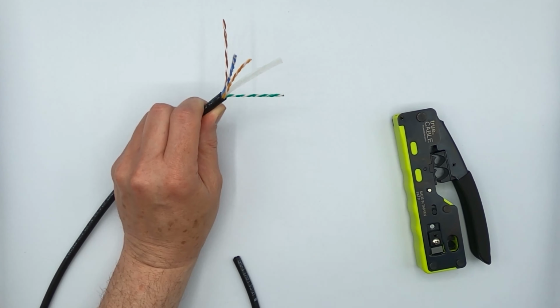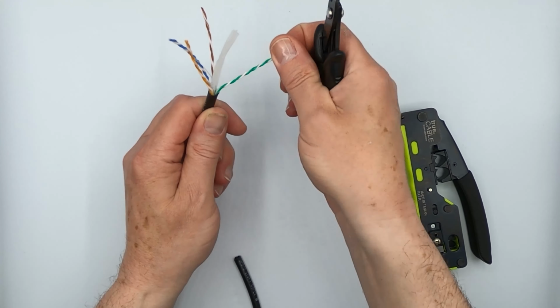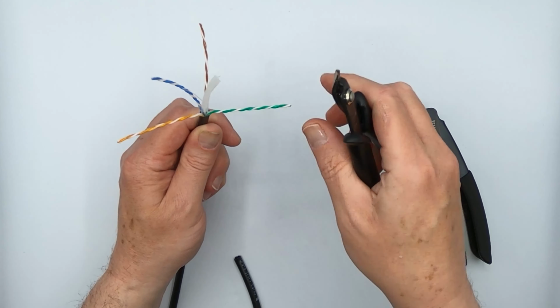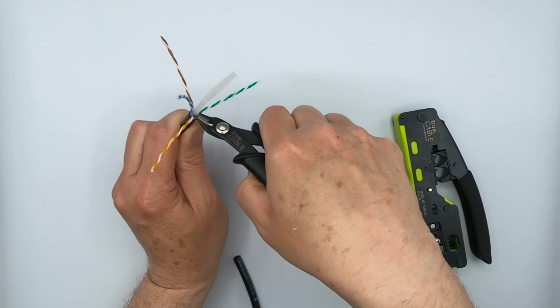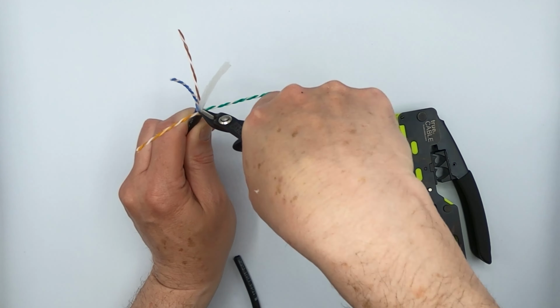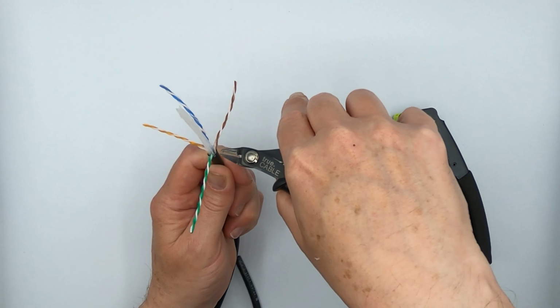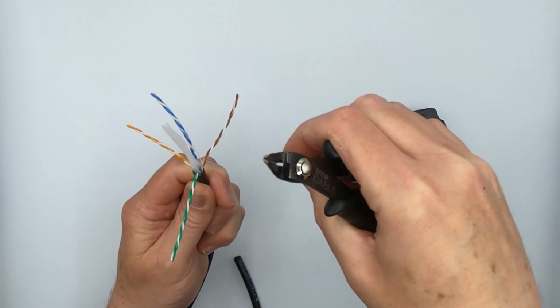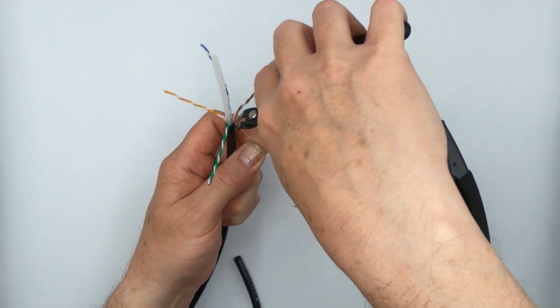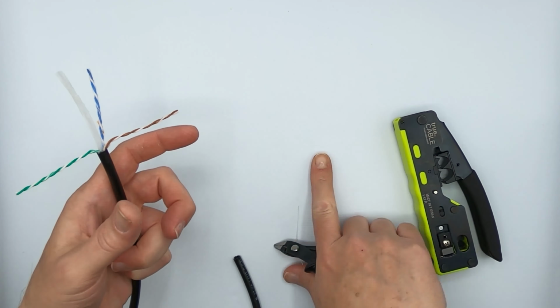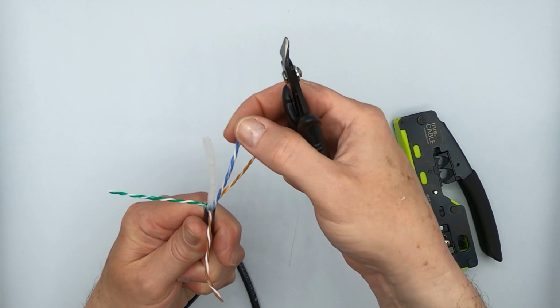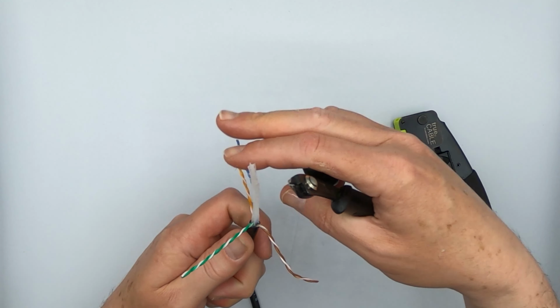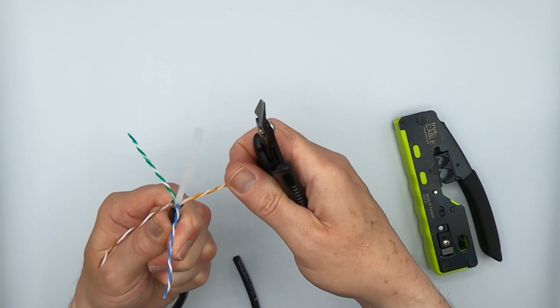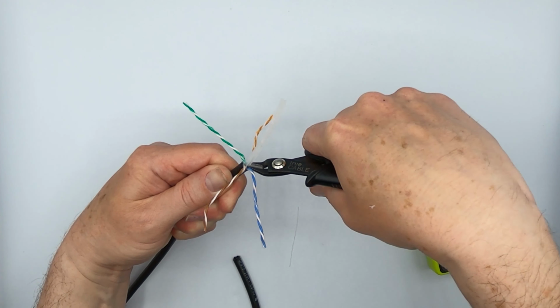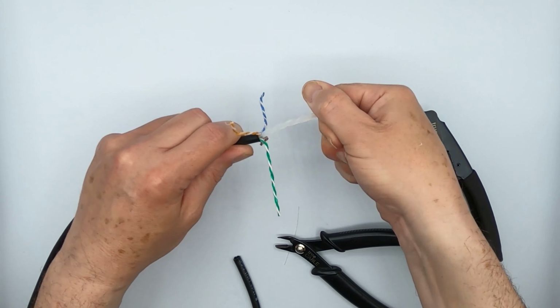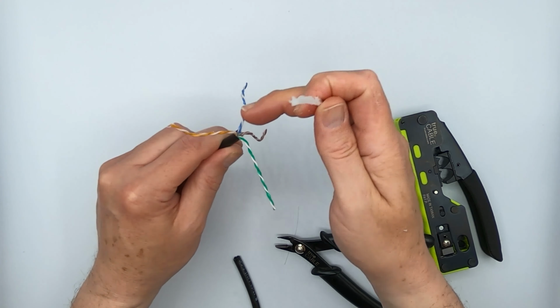So with the spline, generally what I do is I will make 4 snips, one on each wing, at a downward angle, resting the clippers on the cable jacket. The idea is to allow you to get as much of that spline off there as you can. Also, there's a rip cord there. Want to cut that off, get that out of the way as it's sticking to my fingers. And then once you get all these wings cut, then you can twist to remove. And there we go. It's been removed and there's no spline left.